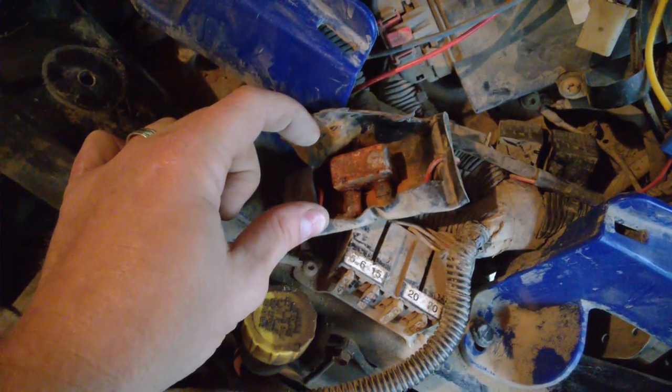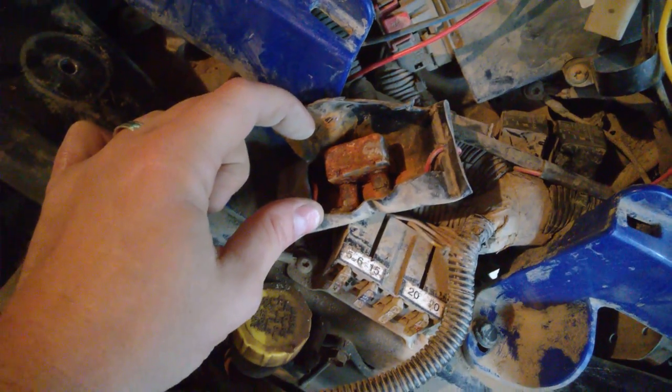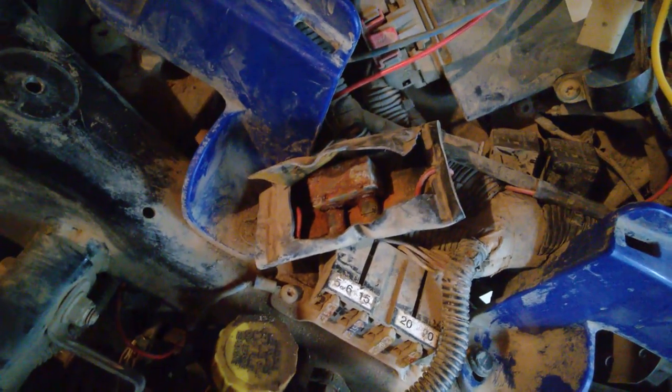You can see there's lots of corrosion inside this little sealed packet where the circuit breaker was. Pretty sure this is shot and is the source of my problem. I'm going to swap it out and hopefully it'll fix my fan issue.